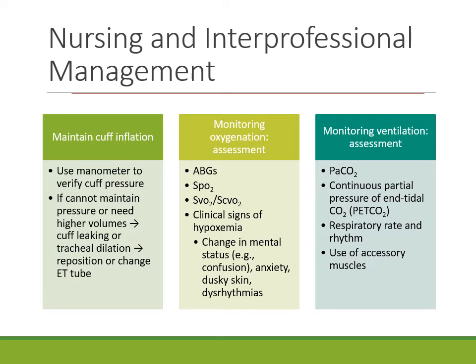Both techniques aim to prevent the risk of tracheal damage due to high cuff pressure. The use of continuous cuff measurement is being studied. Use a manometer to verify the cuff pressures between 20 and 25 centimeters of water and record the cuff pressure and the volumes of air needed to keep the cuff inflated. If increasing volumes of air are needed, the cuff could be leaking, or there could be tracheal dilation at the cuff site. In these situations, notify the healthcare provider.